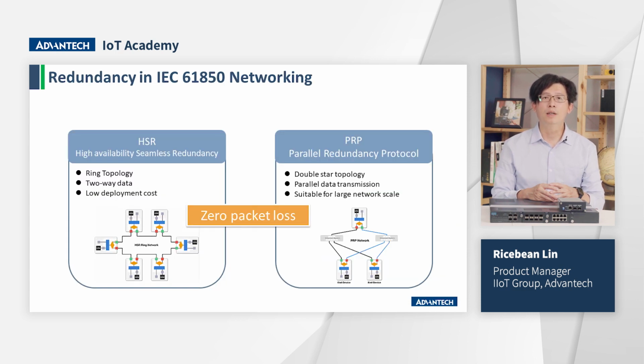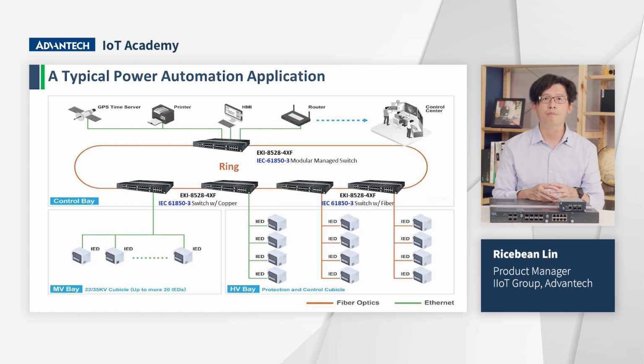The redundancy is also important in the substation. To guarantee the delivery of the information, the IEC 61850 defines two schemes of redundancy, HSR and PRP. Both HSR and PRP are zero packet loss redundancy protocols. HSR is a ring redundancy protocol. It has to be a ring topology, and it can achieve zero packet loss by duplicating the packet. PRP is based on the use of two networks to which nodes are connected. So frames are sent in parallel using the two networks, ensuring secure communication against one failure in the network. Now we are showing an example of the IEC 61850 network.